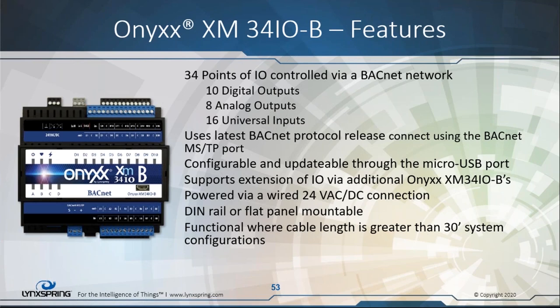It does allow you to extend the I/O further distances away from the Edge device or the Jace device. It has 34 points, again exactly the same type of point structure as Edge 534: 10 digital outputs, 8 analog outputs, 16 universal inputs. The XM, without the B, is Onyxx proprietary driven I/O, and that goes up to 30 feet. When you need to go beyond 30 feet, you can use the XMB.